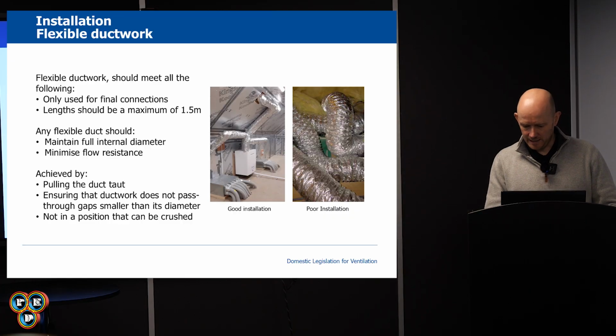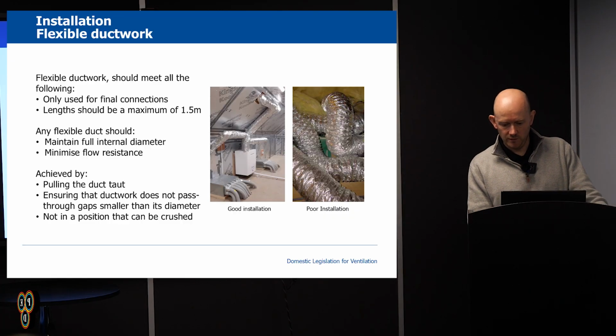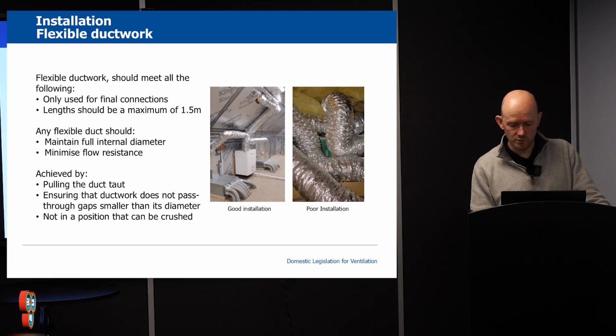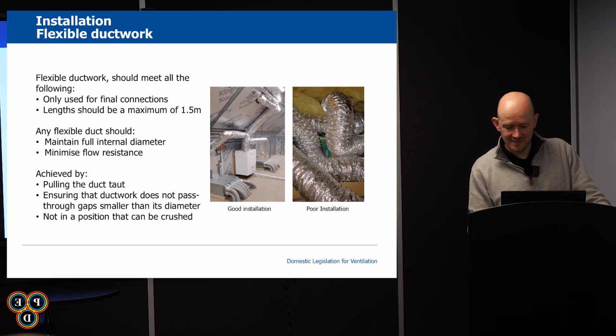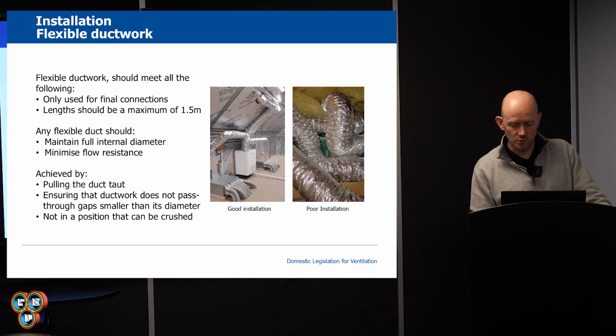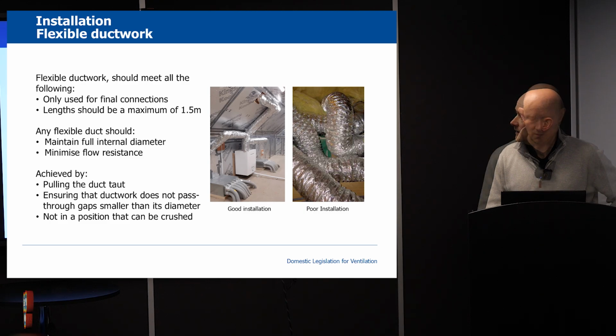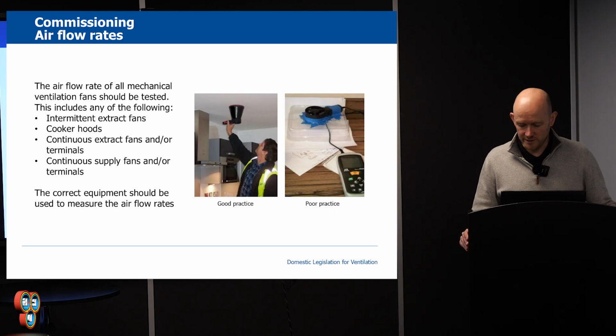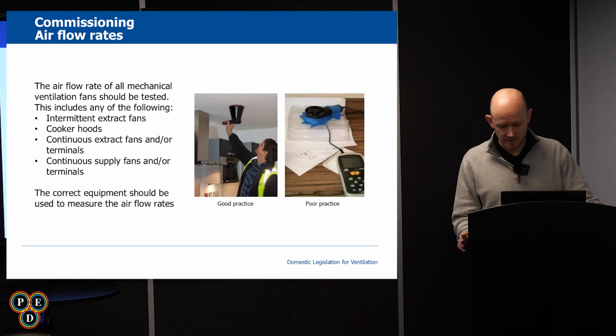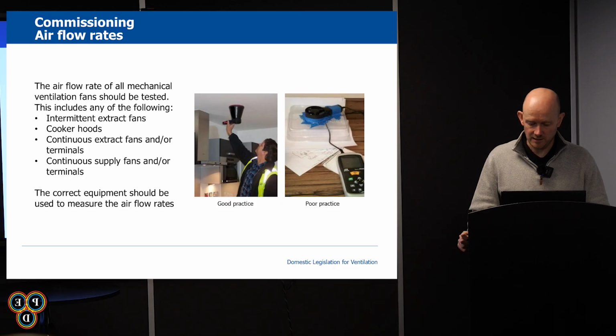Flexible ductwork should be kept to a minimum and ensured that the ductwork is taut, not sagging, nor is it tight, nor has any tight bends to ensure system efficiency. As you can see from the images, the ductwork should be straight and have long sweeping bends where possible, not tangled with multiple bends as per the image on the right. Airflow rates of all installation systems should be tested and recorded with a commissioning checklist.